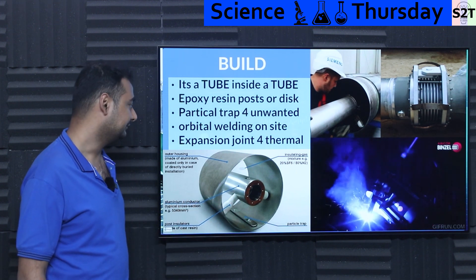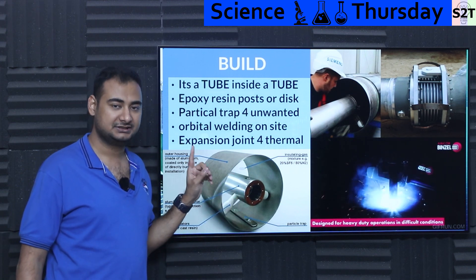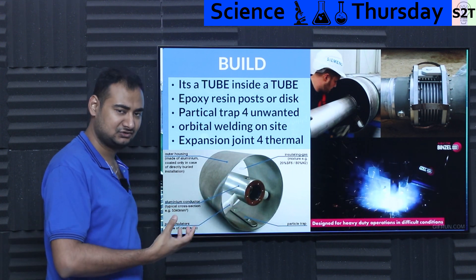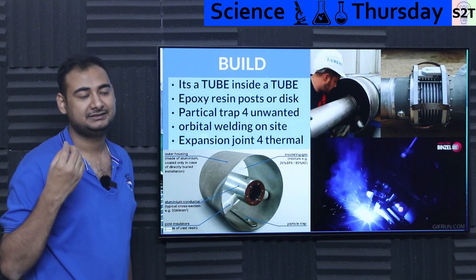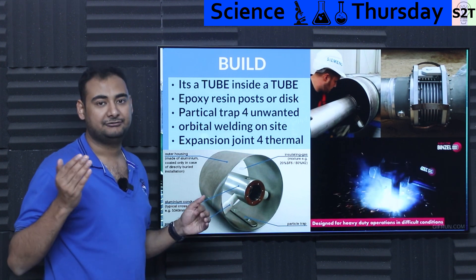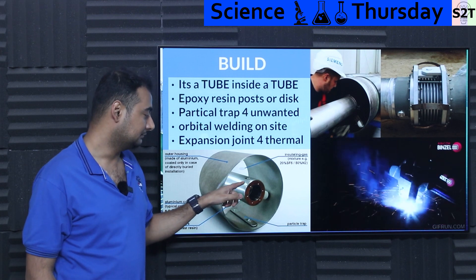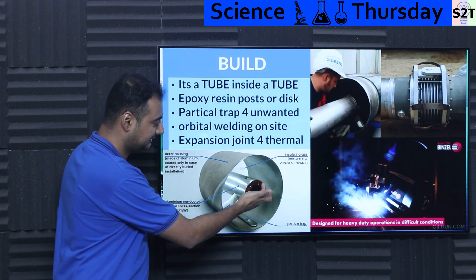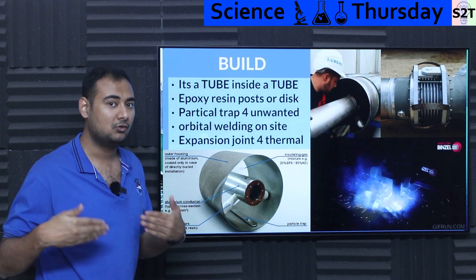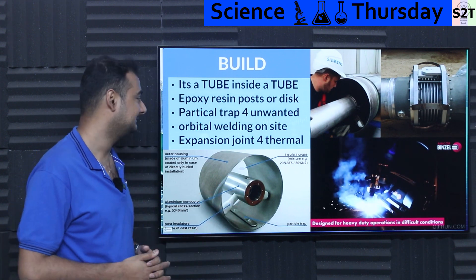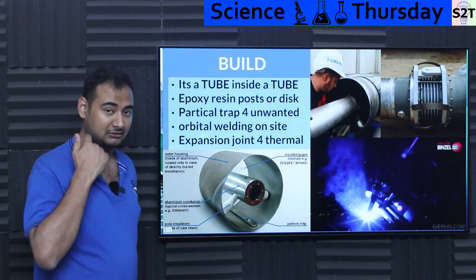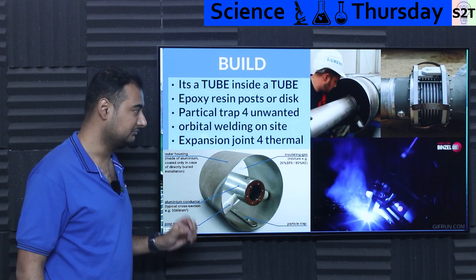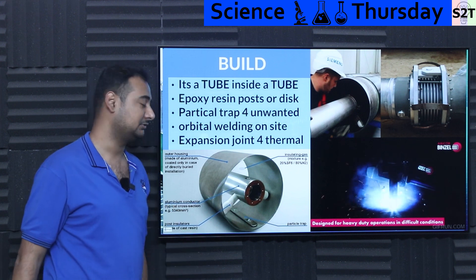The central conductor would rarely be a solid rod — it's generally a hollow tube. Why? Because AC current has a skin effect: the current only travels on the outside of the conductor, regardless of how thick the rod is. At 50 Hz or 60 Hz, you can't use the whole conductor. However, with a hollow conductor, electricity creates a skin effect from the outside and also from the inside, meaning you can carry more practical current. That's why a hollow tube inside a hollow tube is far better. They generally use aluminum — it's not hyper expensive, it's good from an environmental standpoint, resistant to pressure expansion, and resistant to water.